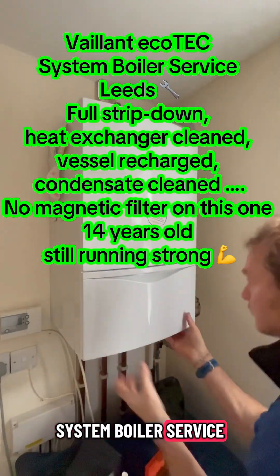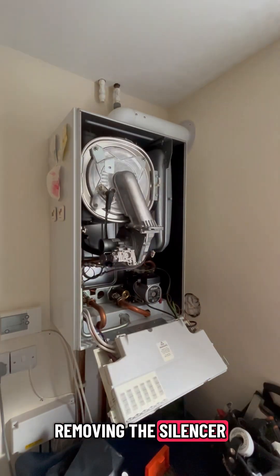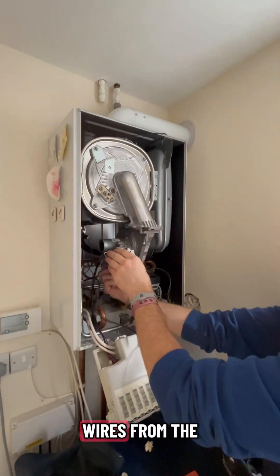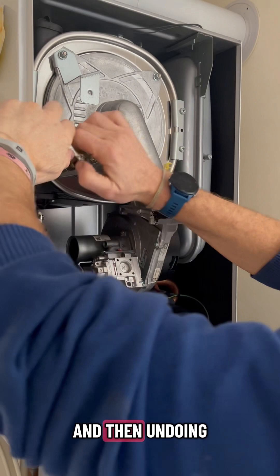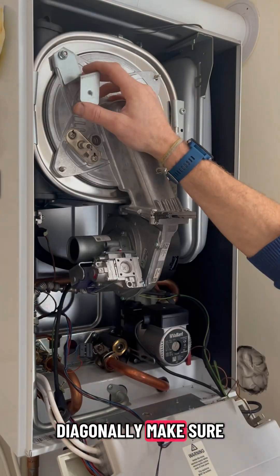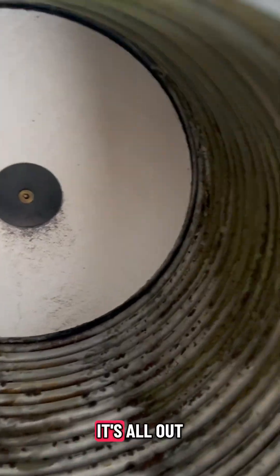Vaillant ecoTEC system boiler service - just getting the case off and then removing the silencer, disconnecting the cables and wires from the fan. Then undoing the screws for the burner door one by one diagonally, making sure it's not stretching too much. There we go, it's all out.